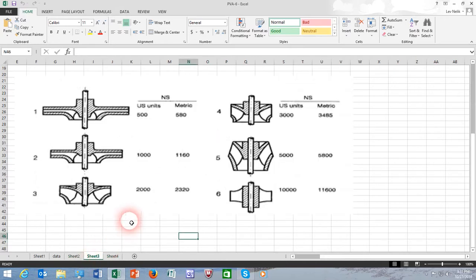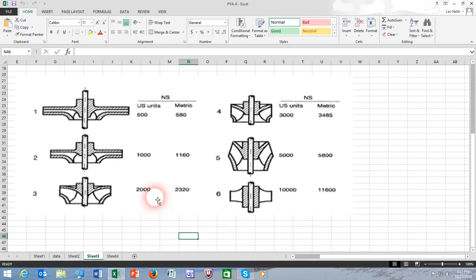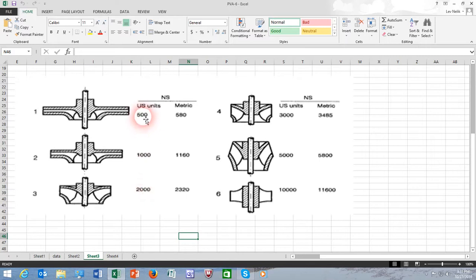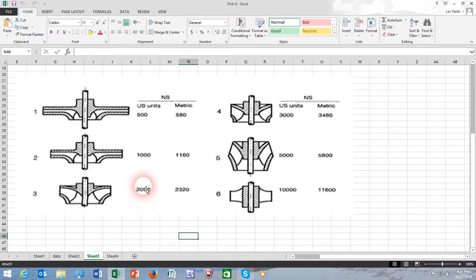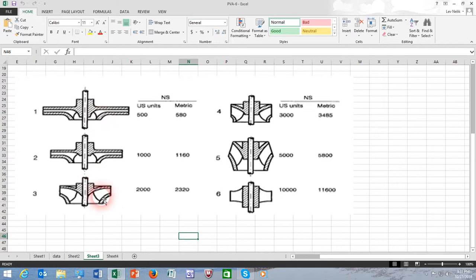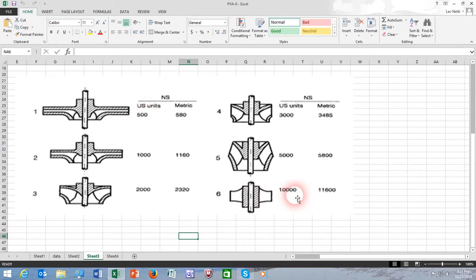Here's another illustration of the same concept from Hydraulic Institute definitions, which tells us that as the specific speed increases, meaning the flow increases and the head drops, as that happens, the pump configuration, as depicted by the shape of its impeller, undergoes transformation from a radial, pure radial impeller, to a mixed flow impeller, to a propeller, and the specific speed is increasing from 500 to perhaps 10,000 or more in the U.S. units.